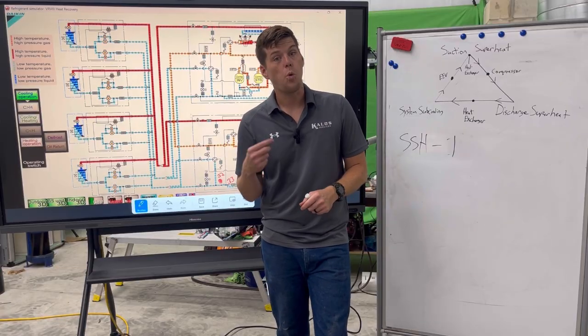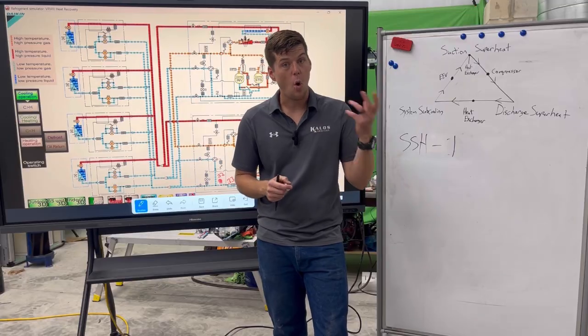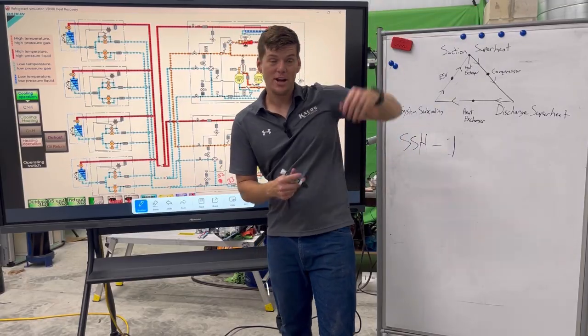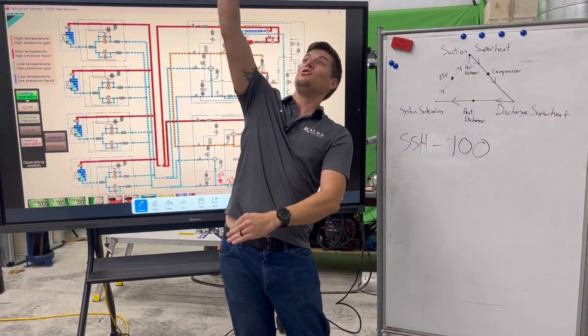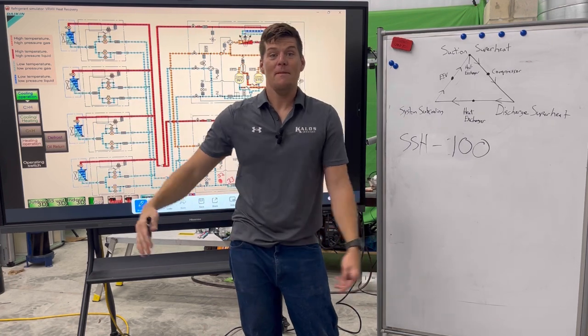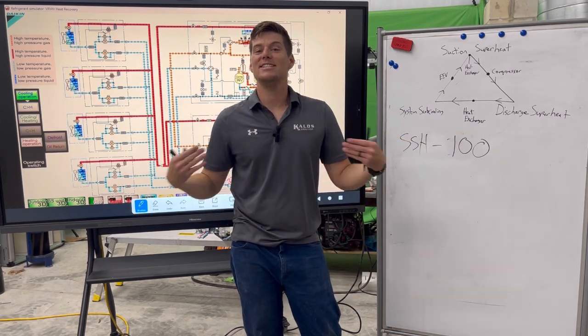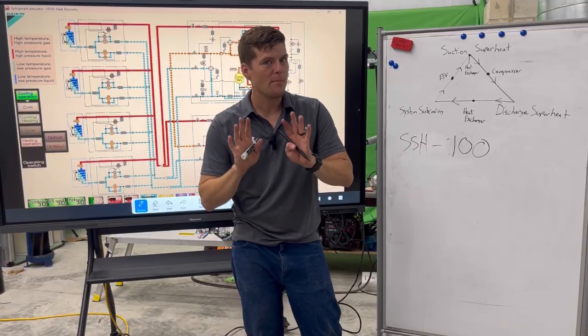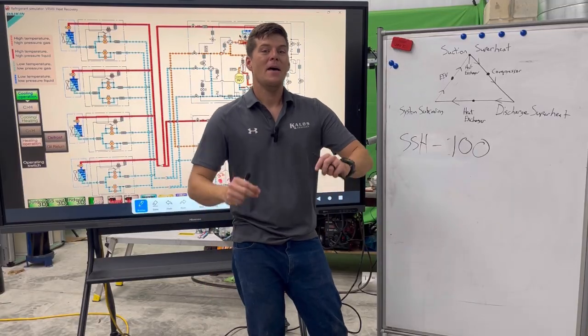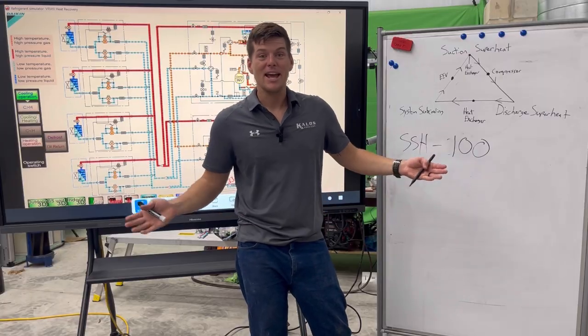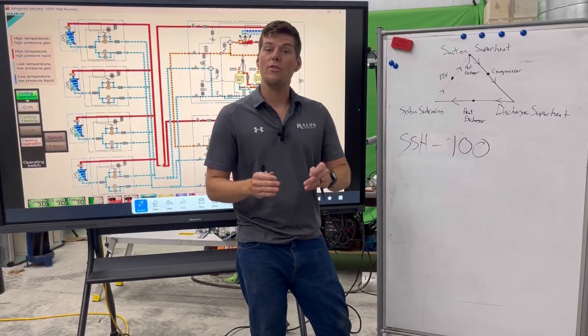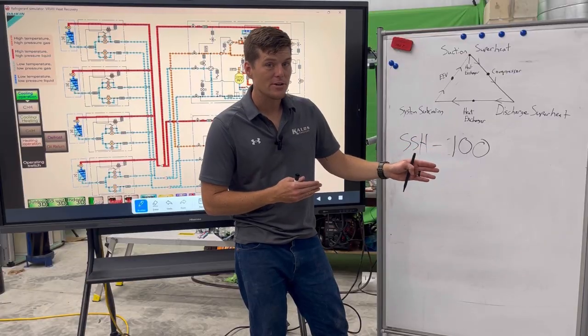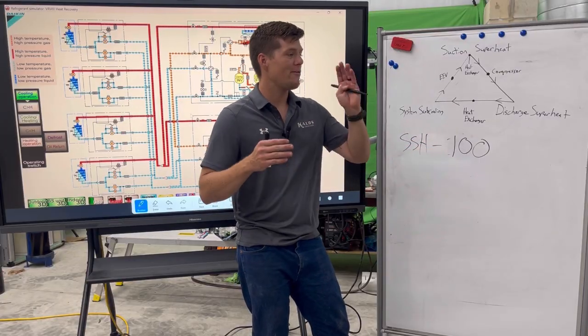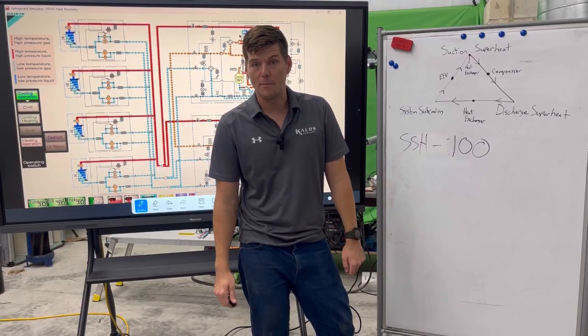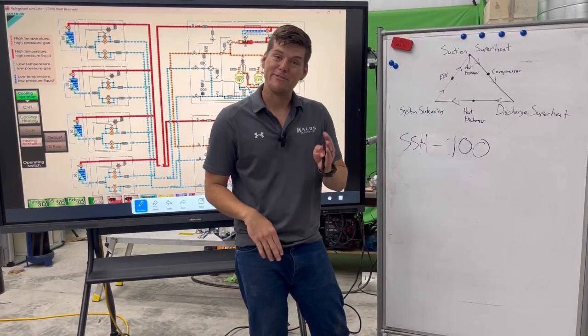The way we measure that quality of vapor, quality is two things. We're measuring the quantity of vapor. If I have a high suction superheat, say 60 or maybe let's say 100 degrees of suction superheat, then my superheat is way up here, which means that my vapor, there isn't any, right? So the quantity is not there. Now the quality might be there. It is 100% vapor. We know that because it's 100 degrees above saturation. However, because it is 100, that tells me that there's not enough of it. We know that when the right amount of vapor is flowing through that line to my compressor, it's in a specific range, usually around 5 to 32 degrees based upon the mode of operation. I like to see it between 5 and 14.